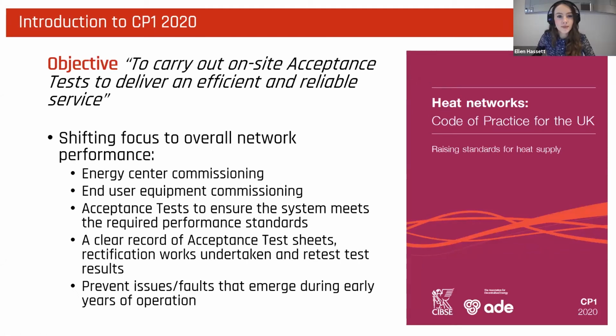Thanks, Freddie. So heat networks play a key role in the decarbonisation of heat in the UK, and the updated code of practice released earlier this year has been written to improve many aspects of heat network from design through to operation. One of the commissioning objectives in section 5.7 details the requirement for acceptance tests to ensure an efficient and reliable service is delivered. In CP1 2020, there has been a shift in focus to overall network performance rather than performance of individual components during heat network commissioning.